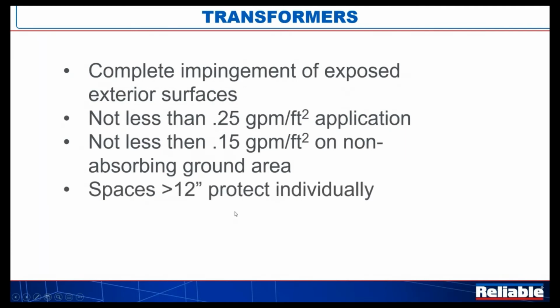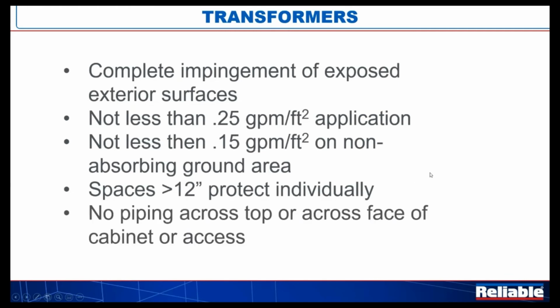Any space, again talking about the modulations, the breaks in, the breaks out, up, down, all these things, any space greater than 12 inches needs to be looked at and protected individually. Transformers, by their nature, and you'll see the diagrams in both 15 and 4-1N, take a lot of nozzles, because there's a lot of different stuff going on that needs to be protected. As you're routing the piping, we want to make sure that we don't go across the top or across the face of what they call the transformer cabinet or any other areas that need access. That makes kind of common sense.